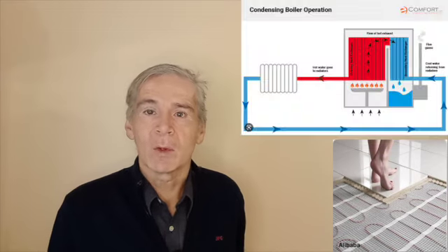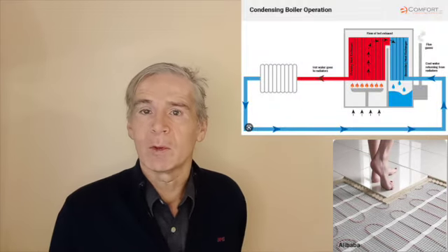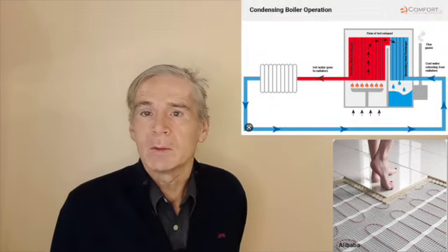Therefore, try to pick applications where this condition is fulfilled, or change the situation so you can use the heat pump. For example, working with low temperature heating systems like floor heating adapts the demand side to lower temperatures. Condensing boilers also require working with low temperatures, so nothing new.